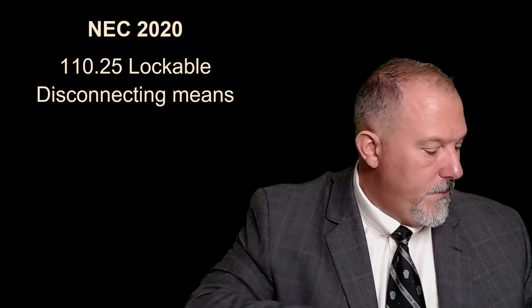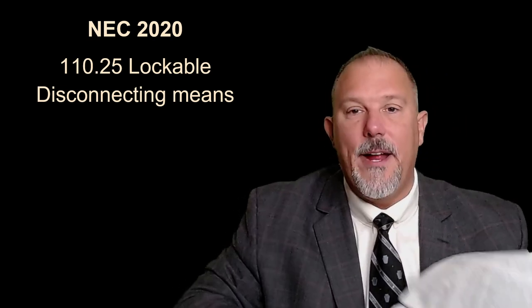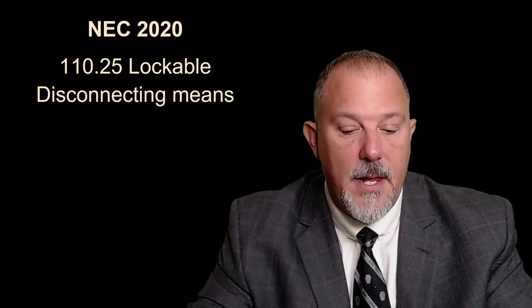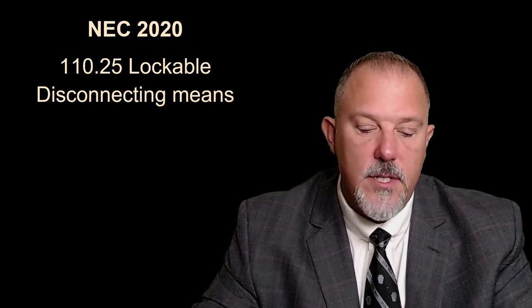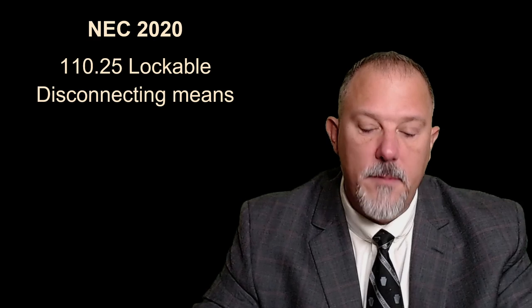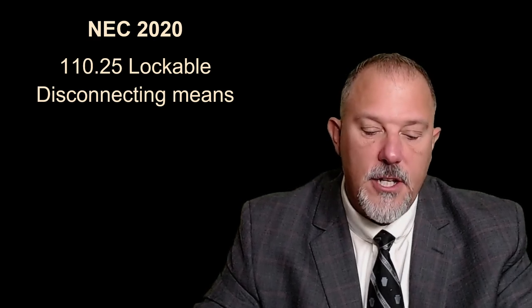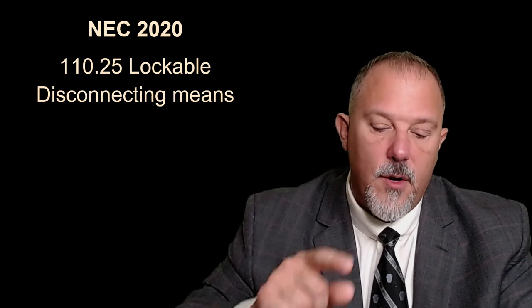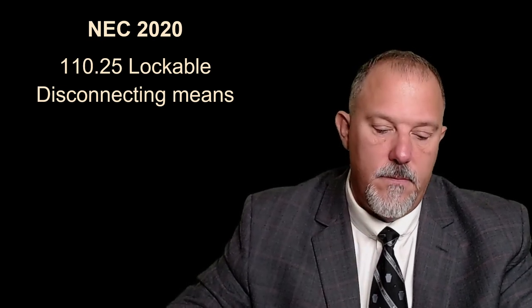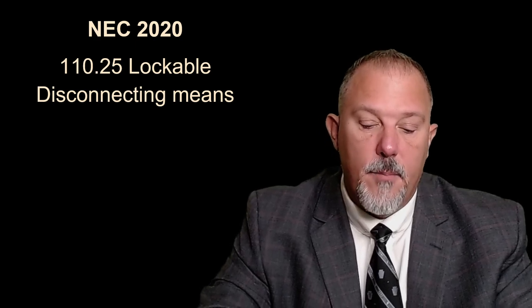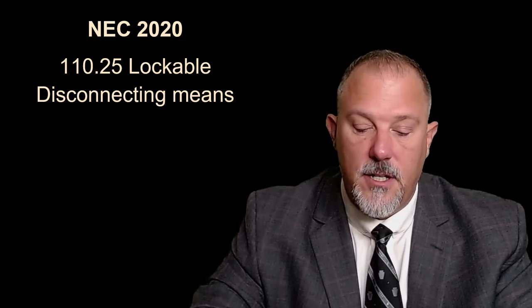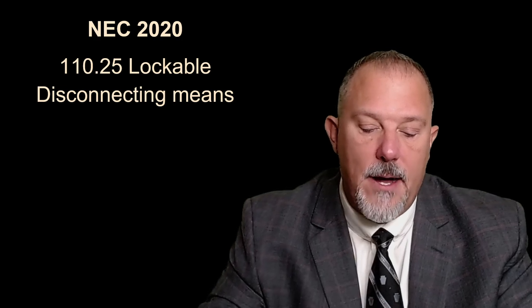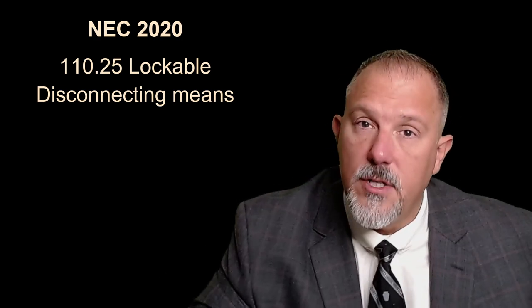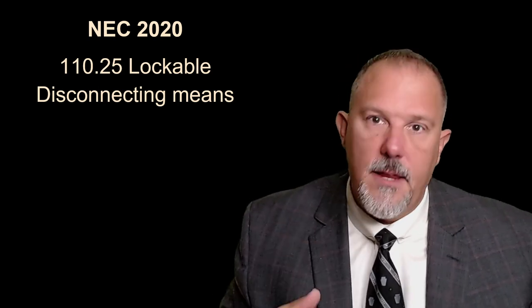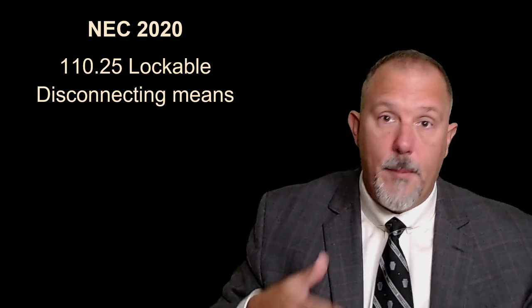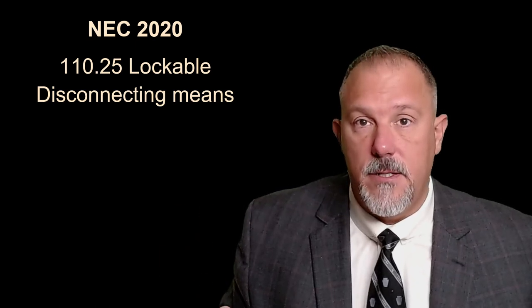110.25 tells us, if a disconnecting means is required to be lockable open, elsewhere in this code, it shall be capable of being locked in the open position. The provisions for locking shall remain in place with or without the lock installed. And the only exception to this is locking provisions for a cord and plug connection shall not be required to remain in place without the lock installed. So circuit breakers and other switches have to have the provisions permanently there so that you can apply your lock and do your lockout tagout process.